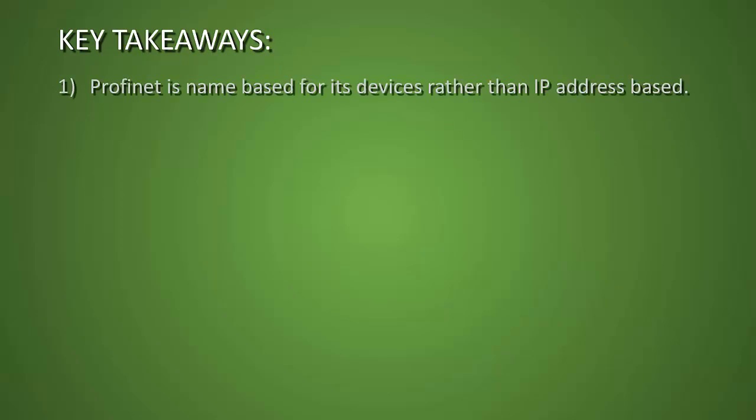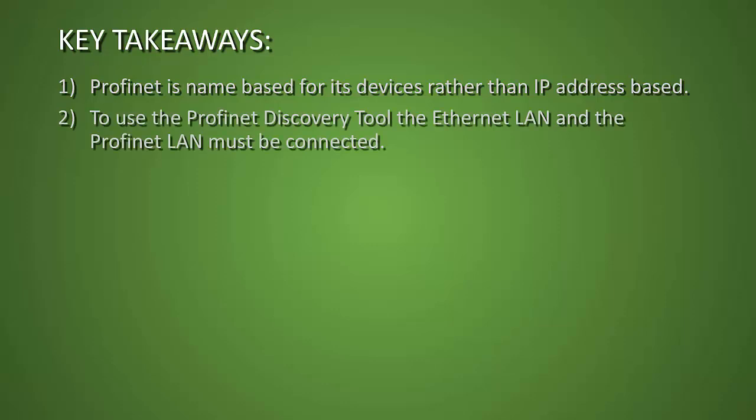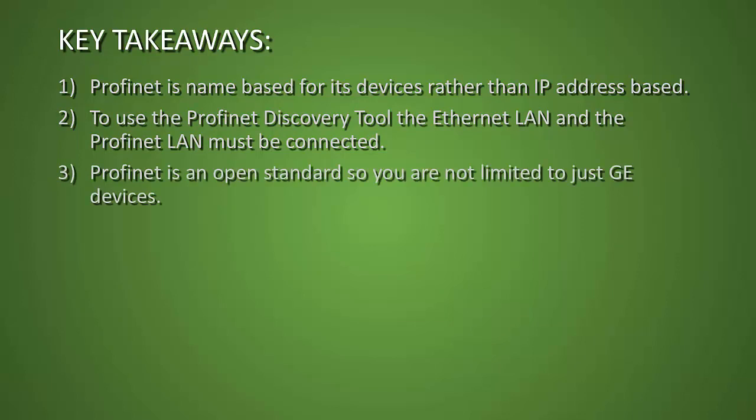A few things for key takeaways. First off is that PROFINET is name-based for its devices rather than IP address-based, so you want to make sure that you get your names correct to make it work properly. Secondly, to use the discovery tool, the Ethernet LAN and the PROFINET LAN must be connected. And finally, PROFINET is an open standard, so you can use lots of other manufacturers' devices with your GE system. All you need to do is go to their website and download the PROFINET GSDML file and add that into your system.